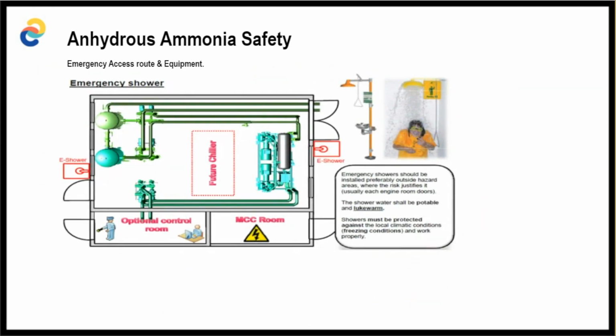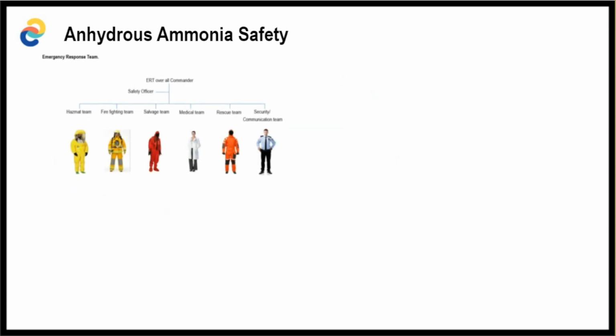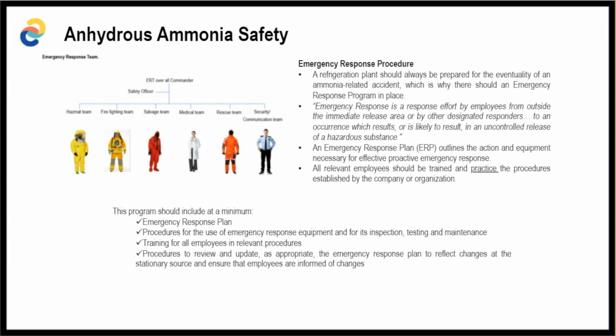Another best practice is that each machinery room shall have access to a minimum of 2 eye wash or safety shower units. Establishment of an emergency response team should an ammonia-related accident occur. They should have a response plan, first aid, and people with assigned tasks should the emergency happen.